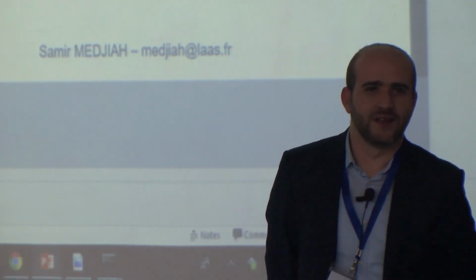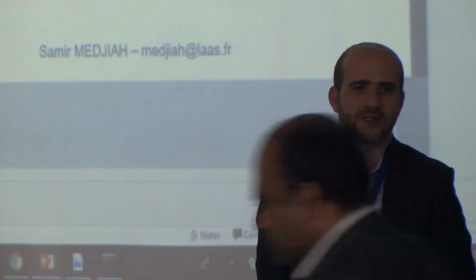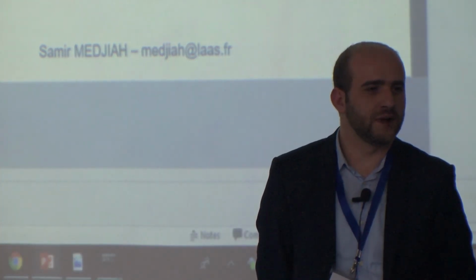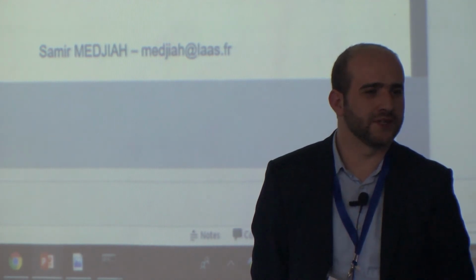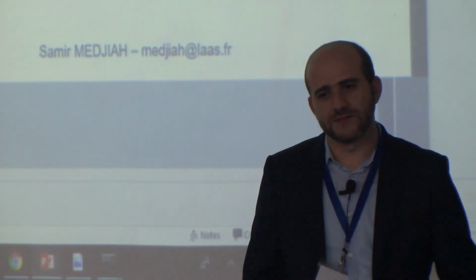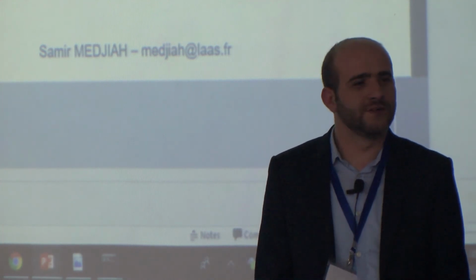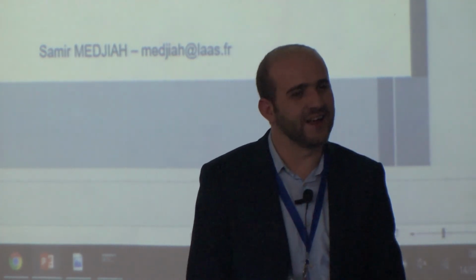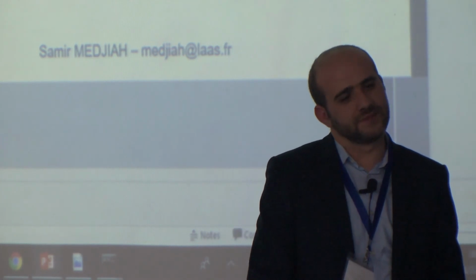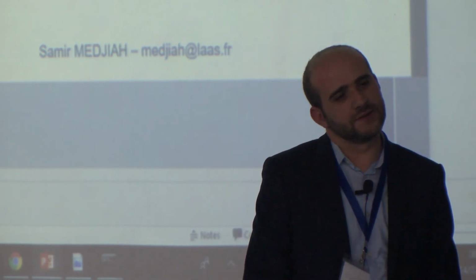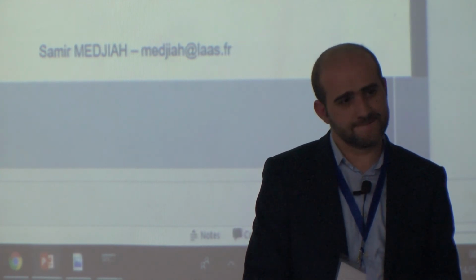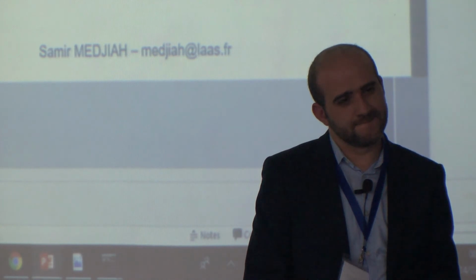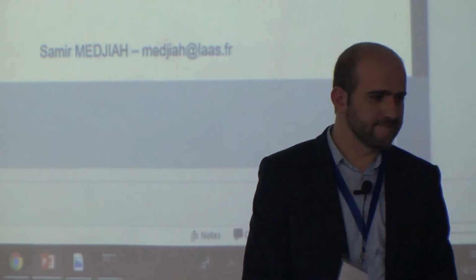The question you're asking is: can we do control commands using an API based on RESTful API? Short answer, no. When you have the MPM in between, the client being a RESTful API is okay. But when the MPM talks to the transducer, that is the actuator, if you're trying to do some sort of control, then the state machine between the MPM and the actuator is most important.